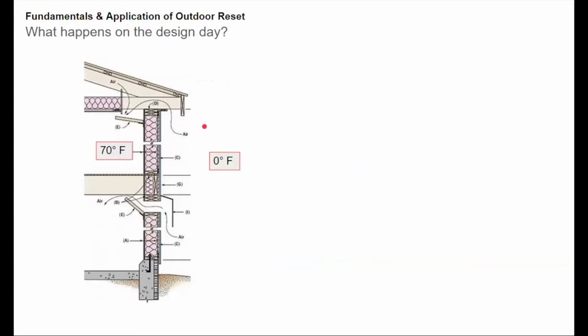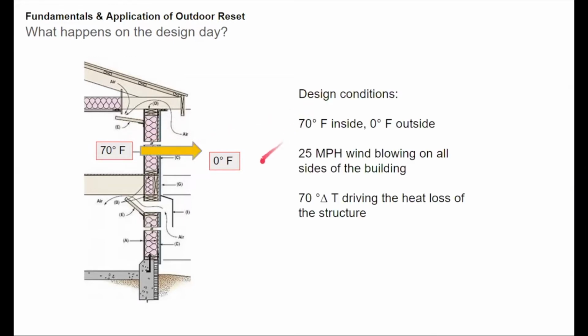through the envelope. So let's say that we're designing for a 70-degree temperature on the inside, and let's say we're designing somewhere around 0 degrees Fahrenheit. For me, that's somewhere around Boston, Massachusetts, up to probably southern New Hampshire. So we select our inside temperature. From ASHRAE data, we pick our outside temperature, and then that delta T, or that differential temperature, then sets the rate of heat loss. Now, from an aspect of design, we don't just look at the delta T, we also look at the wind speed blowing on the building, because that affects heat loss as well.